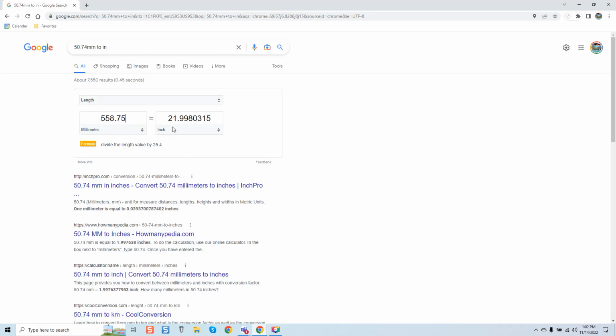It was interesting. We used a 1-inch dial indicator, and all of a sudden we have perfect at 1 inch like nothing. As soon as we do 22 inches, you're going to find those tolerances are going to be really true when we use a tool like this, because, again, all those hidden discrepancies with machining, once again, screw tolerances, and just inevitable variables are now coming to fruition. So, again, it's very, very interesting. Whenever he's ready, you go for it, Mike. Okay. Yeah, you could put in, let's do it, we'll do a regular calibration. Let's put in 21.9980315.